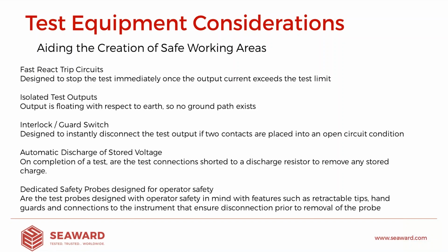It can also be used in many ways to create your area with automatic protection and to keep the untrained out. So in many instances, people will use this guard switch to link it to the doorway to the area, for example. So if someone wants to walk into the area, instantly that test voltage is disconnected and the area is safe to go into use.